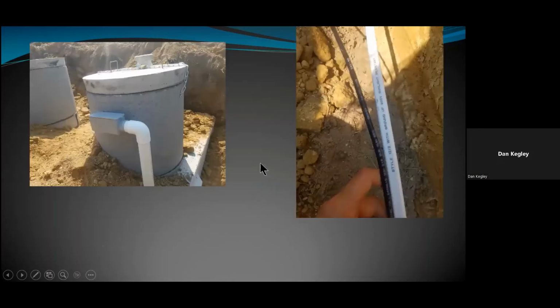All right. So a good picture on the left here. They've got an LB, or actually this could be an LL or an LR because it's coming out the side. The code says there's not enough space in this LB to put cord connectors and receptacles and things inside this area. It needs to be a junction box. In addition, if you look at the ground level here, is this going to be buried or is it going to be right to the earth? Because this is not a waterproof box, right? So it's not going to keep the water out.